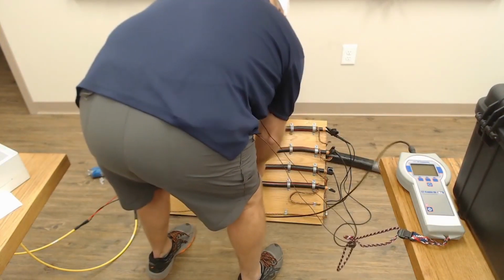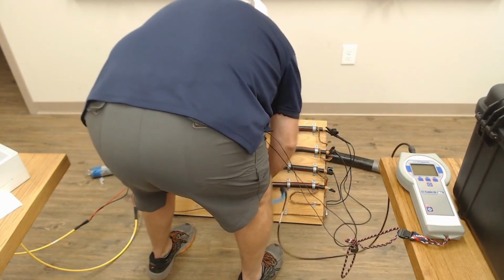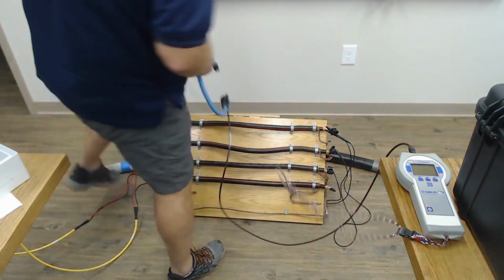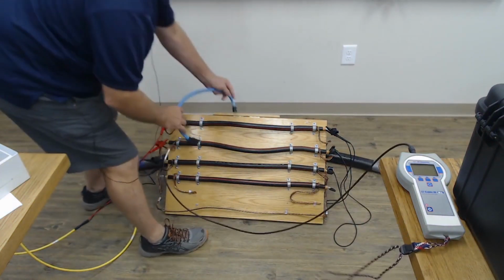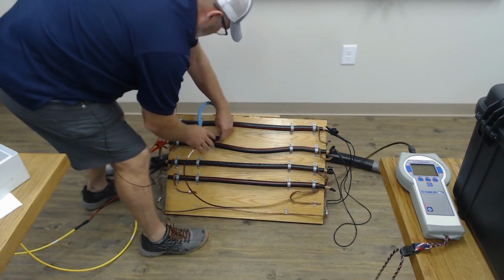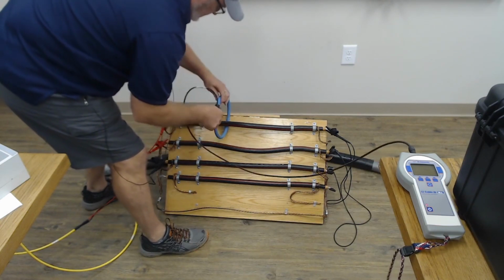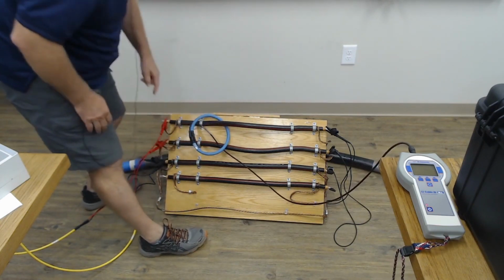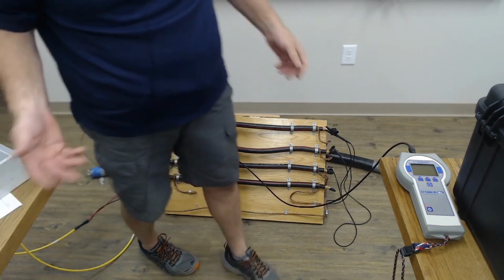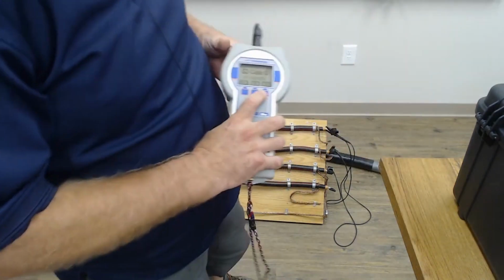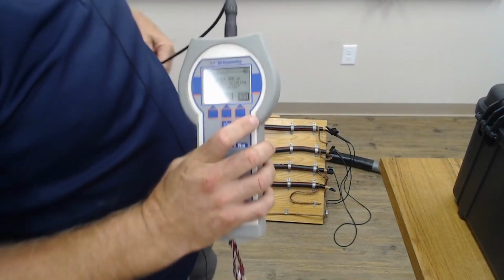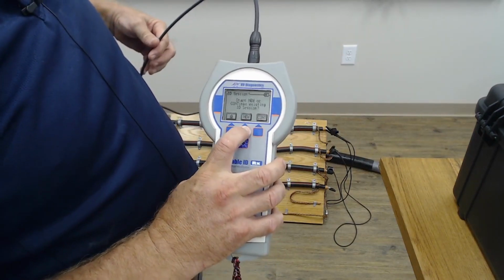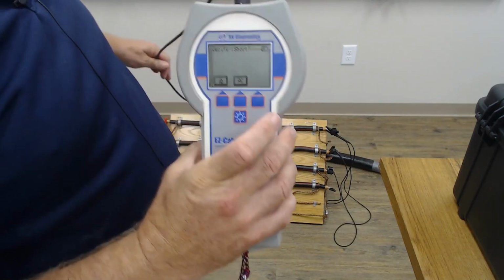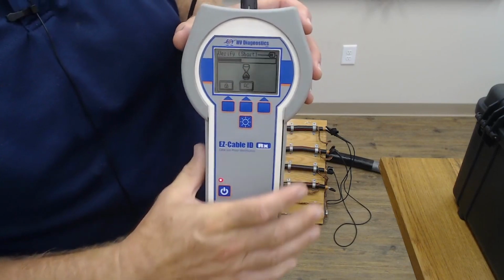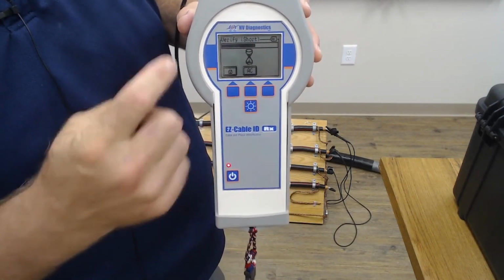First of all, we go to the known point on the cable. So this cable is pretty short, but you get the idea. We'll go to the known point, which is here. We know for a fact that this is L1 over here, because we write at the, let's call it the breaker or the riser. We know it's L1, and we say to it, please go and identify this cable. So here we go. And it should say L1 question mark.